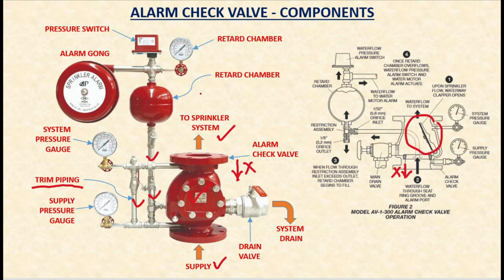So next we have the retard chamber. This one, see, retard chamber actually. This part. So the retard chamber basically prevents the alarm from being triggered by minor pressure fluctuation in the water supplies. This delay mechanism ensures that alarms are only activated when there is sustained water flow, reducing the likelihood of false alarm. So in a system, suppose we have very minor pressure fluctuation, then this alarm will not sound unless we have some big water flow. That means suppose one sprinkler is broken, then only this water gong will fire and sound an alarm.